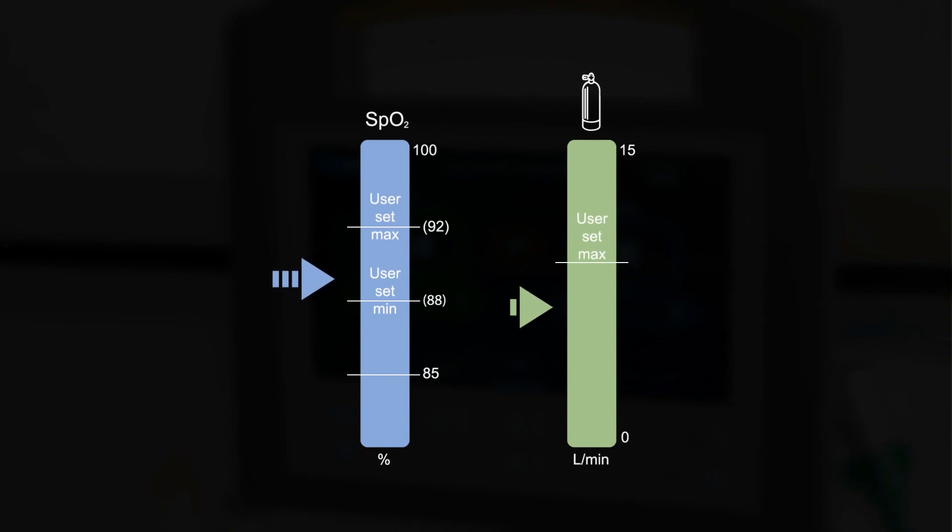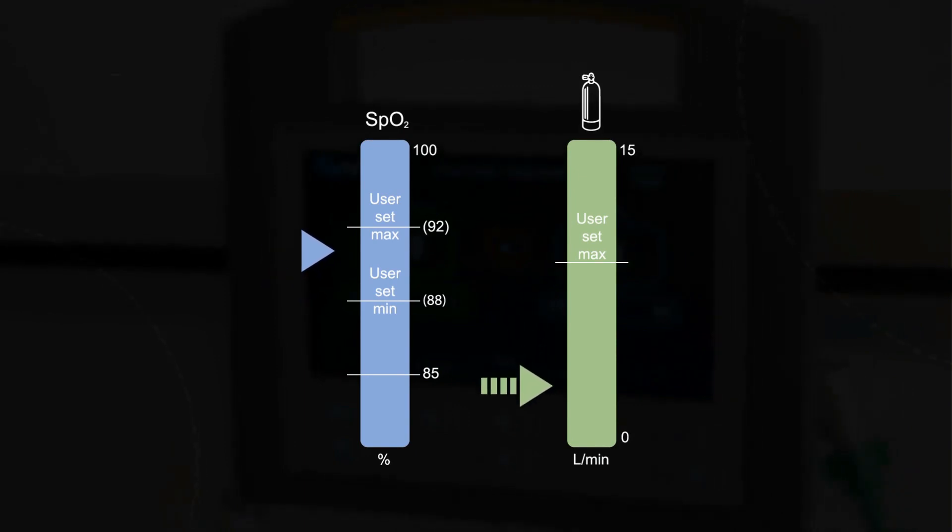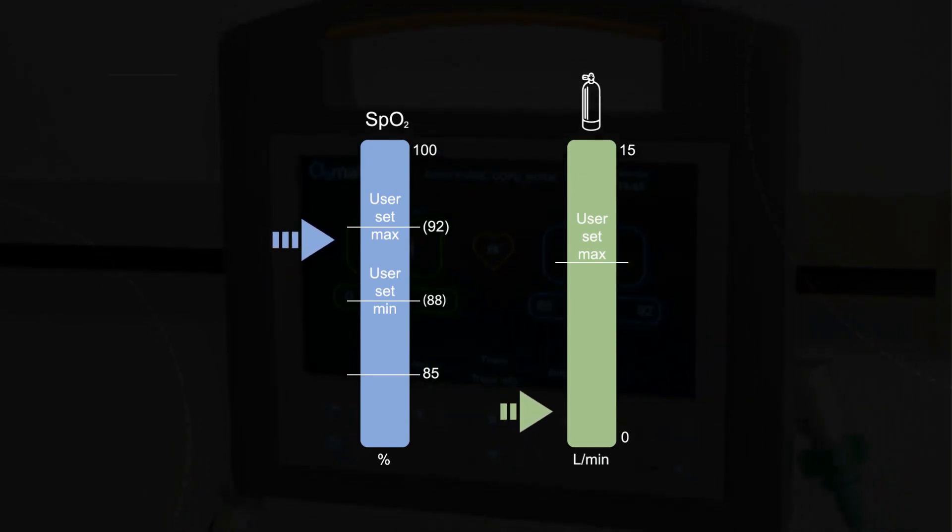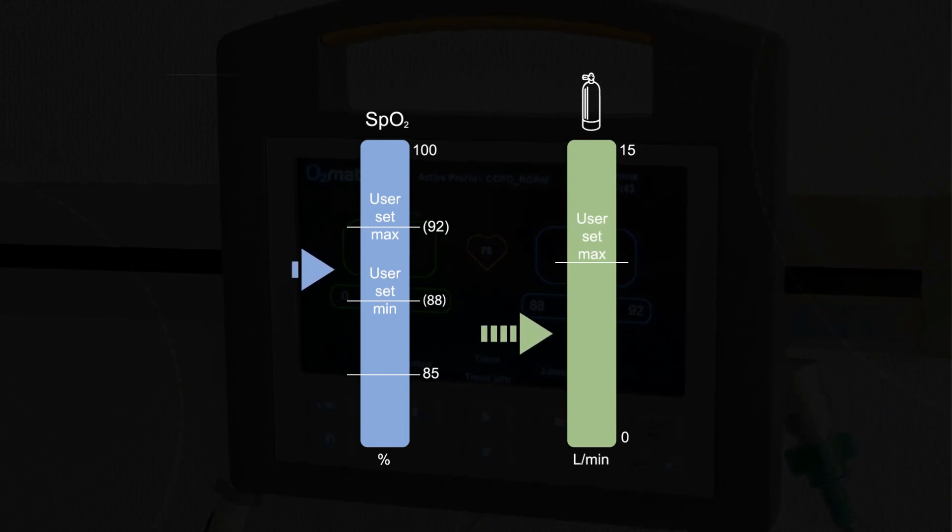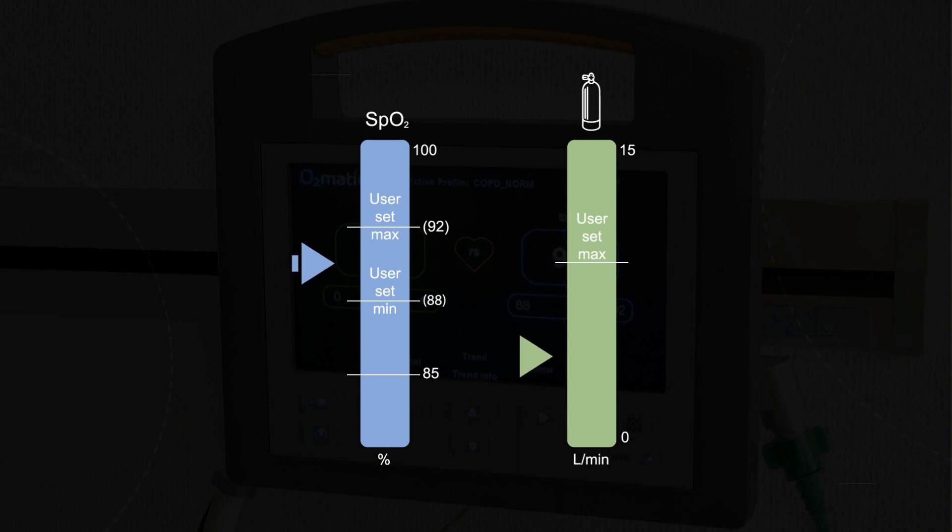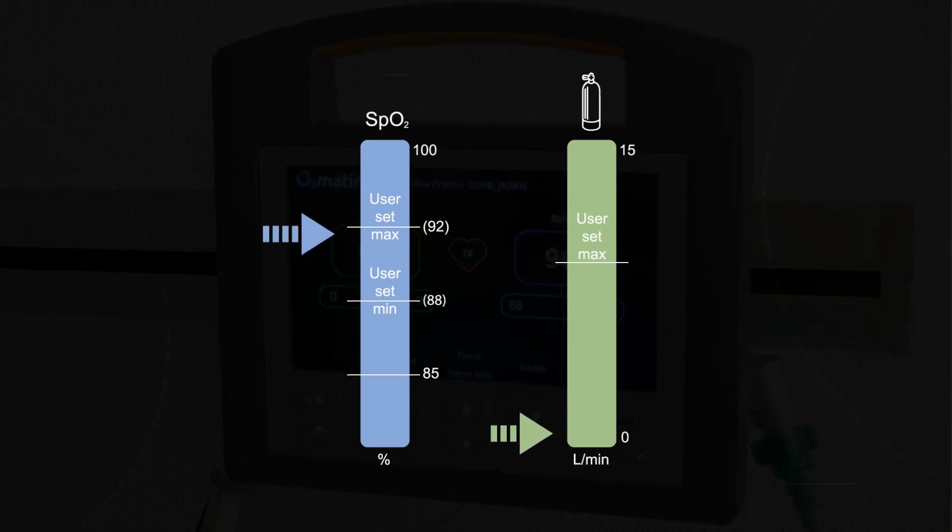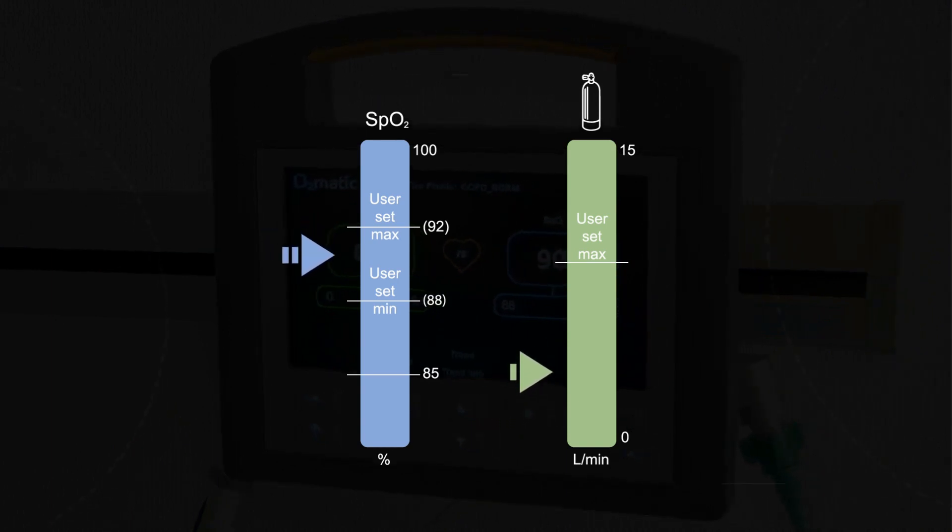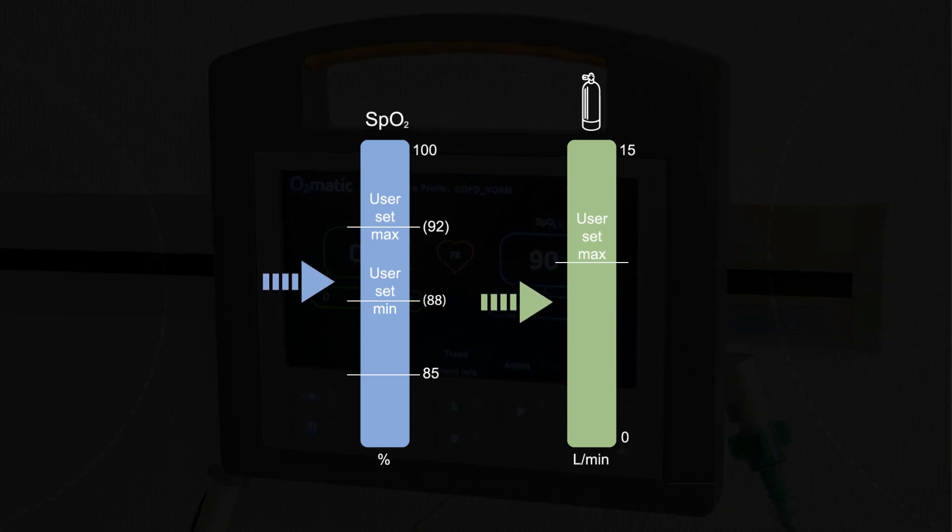O-matic is a closed-loop system which continuously measures the patient's oxygen saturation by pulse oximetry and adjusts the oxygen flow to maintain the saturation within a target interval. O-matic is designed for hospital use and in this study it was used on respiratory wards for patients with COPD.